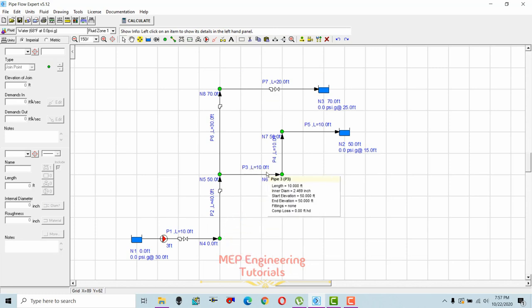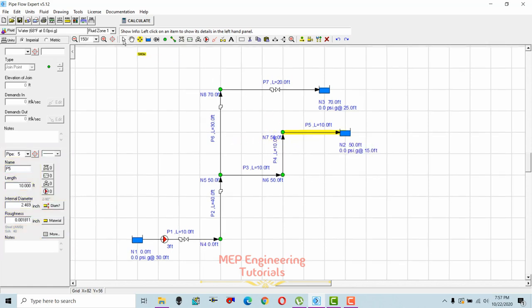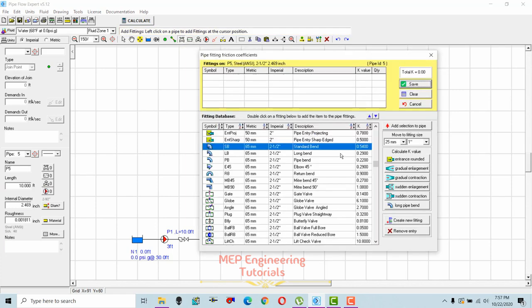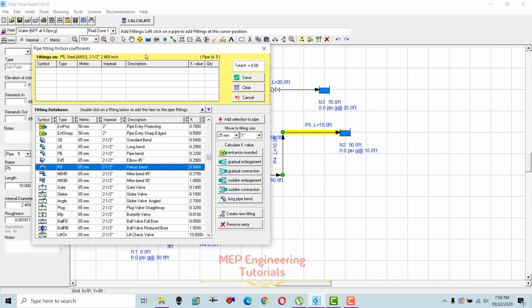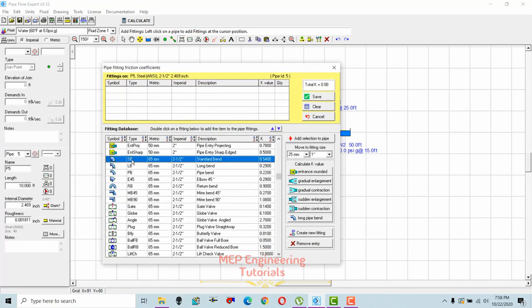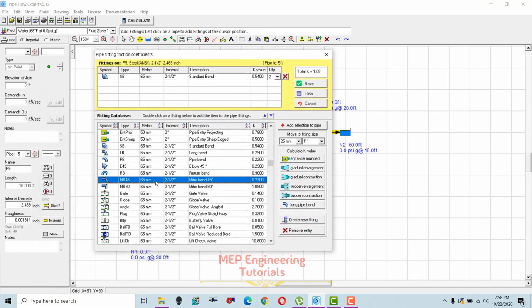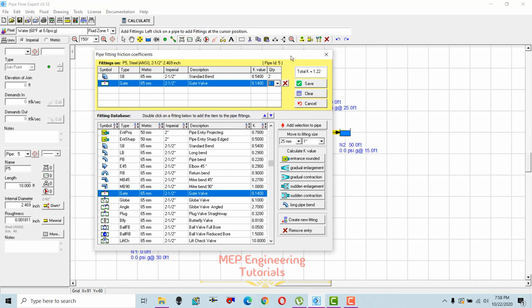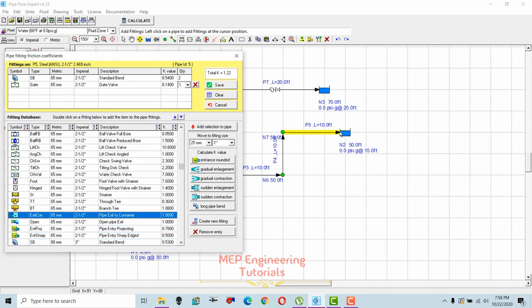For the remaining pipe segment, add fittings: two elbows (standard bend, 2.5 inches, quantity set to 2), one 2.5-inch gate valve, and a pipe exit to container fitting at the tank end. The total K-value for this segment is 1.22. Save it.